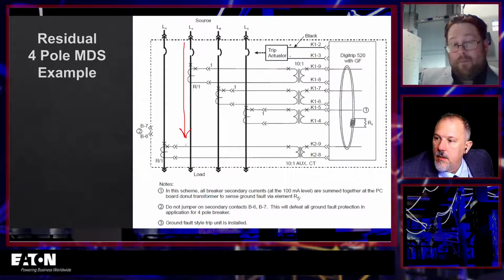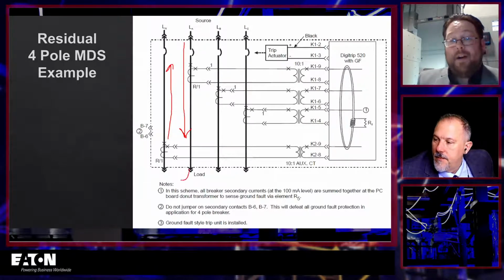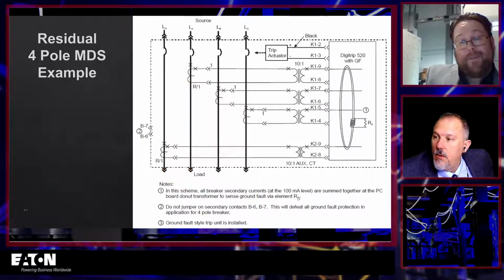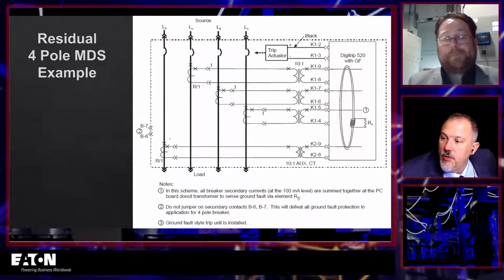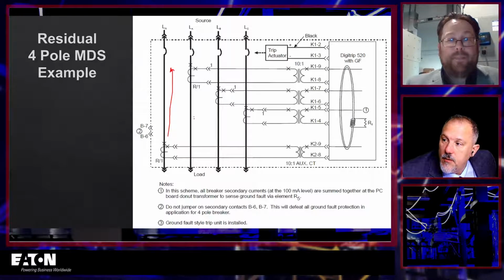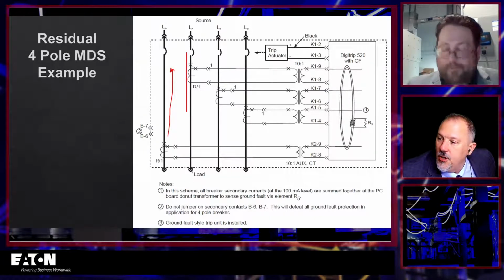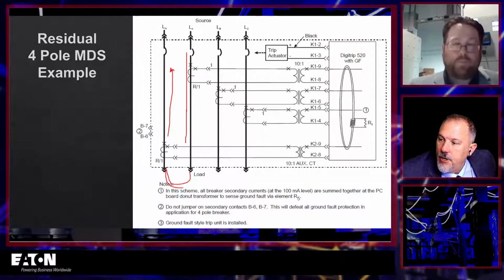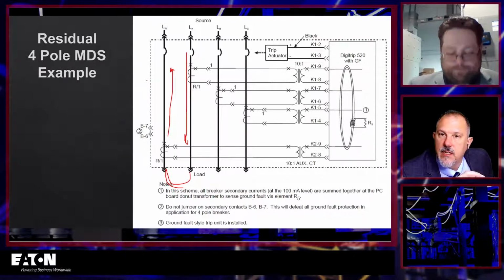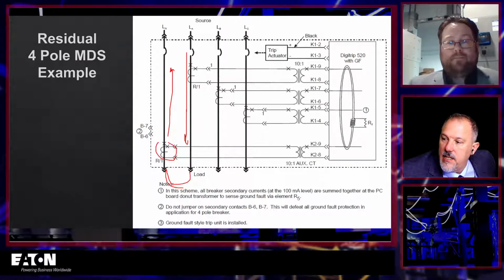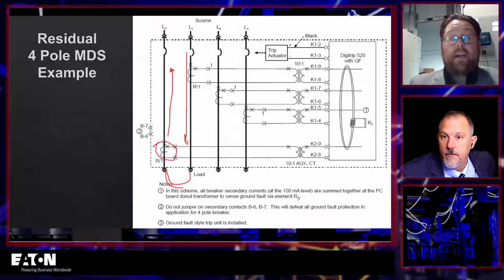Right. When we then put the neutral into it, we should have the arrow pointing up on the neutral. That should be no trip. If it trips, that means the wires on that neutral sensor are flipped on the secondary side. Oh, okay. We need to confirm that. When you're going through the neutral this way, are you also putting current through phase A? Yes. So you're basically jumpering this right here, and you're sending current down that way and back up through that neutral, and that should not trip because both of those CTs are seeing the same thing. And that confirms that this CT is correct, whether it's in the breaker or outside of the circuit breaker, it's the same type of test. Yes. Perfect. Exactly.